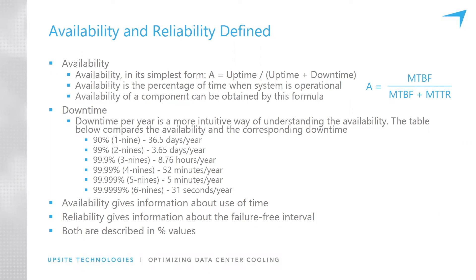MTBF is typically determined using individual system components, working out from a manufacturing perspective what their likely lifetime is and when they're likely to fail. MTTR — meantime to recovery — is typically about a service rather than a system. When talking about data centers, we need to be very careful when using percentages: are we talking about power, cooling, network, or IT service availability? Without that definition, the term is pretty meaningless.